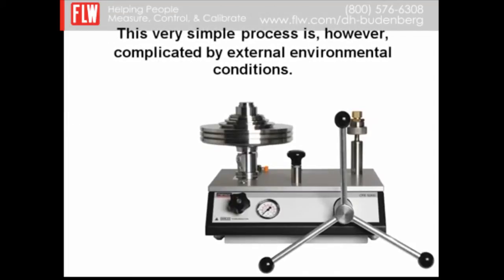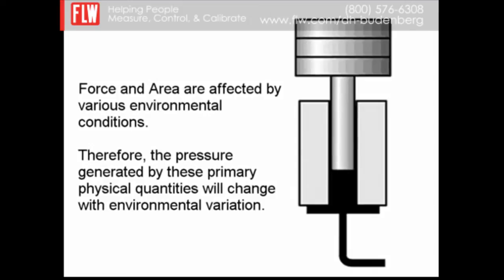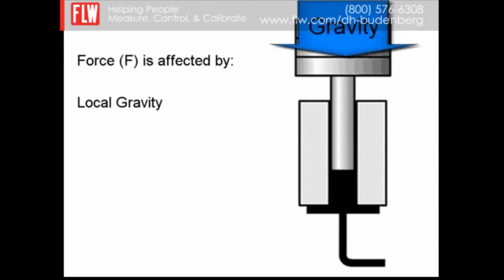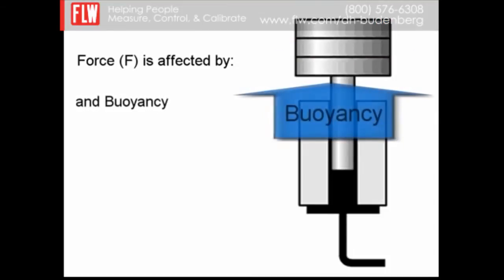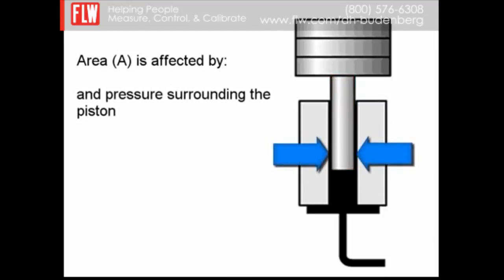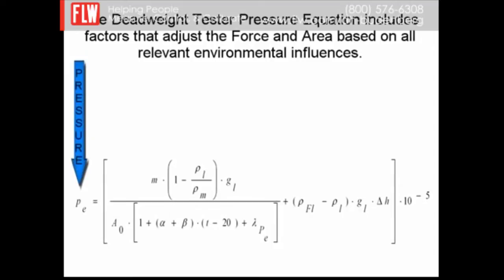These are very simple principles but complicated by environmental conditions. Force and area are affected by various environmental conditions. Force is affected by gravity and buoyancy. The area of the piston is affected by the temperature of the piston and the pressure surrounding the piston. The dead weight tester equation includes factors that adjust for the force and area based on all relevant environmental influences.